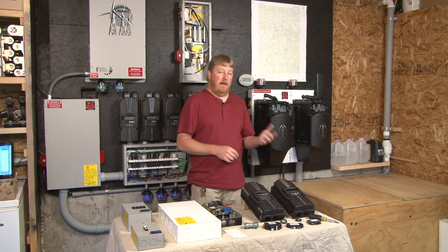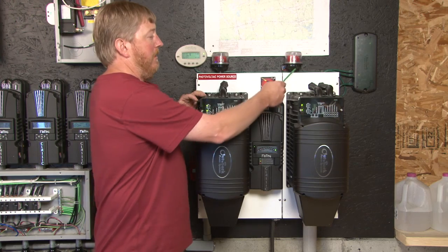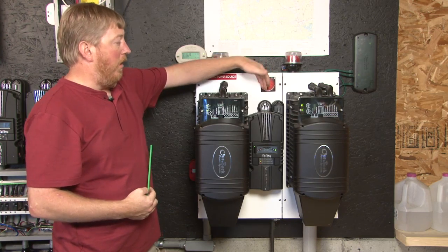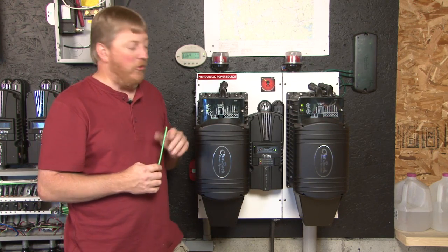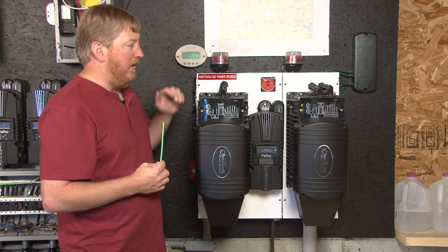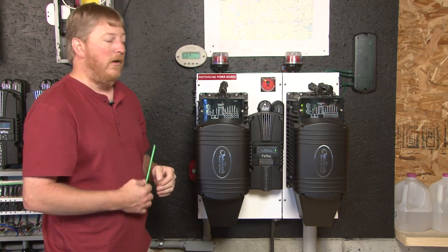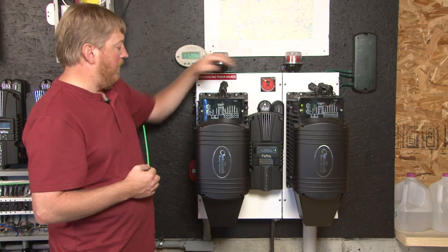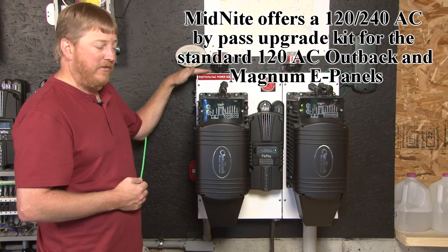I want to go over to my Outback inverters and ePanels on the wall. Here we have my two Outback inverters that are powering my house. We have a narrow Outback ePanel, we have an Outback plus ePanel, and we have the Classic on the plus ePanel. A unique feature of the MidNite plus ePanel is the Classic mounts right on the door with the Outback inverter to save space. These two ePanels bolt right together to make a nice compact 120/240 system. The Classic integrates right into the door, with plenty of room for overcurrent protection on both sides and room for lightning arresters and MidNite Solar SPDs on the top.